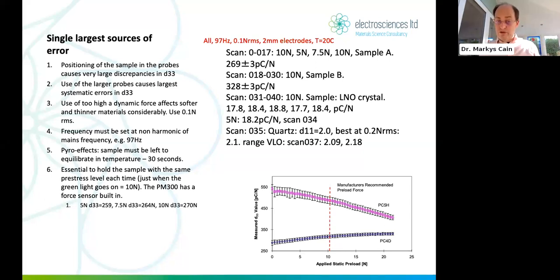And if you look at this graph on the bottom right, you can see real data, okay, for a soft material on the top and the hard piezo material on the bottom. And the y-axis is measured d33 value, and the x-axis is static preload in newtons. 10 newtons is the manufacturer recommended preload. Now you can see that the hard material is not so dependent on preload. It is a bit, but it's not so dependent. But the soft material is much more dependent, very much more dependent, and even a few newtons difference can impact your measured value by a lot.